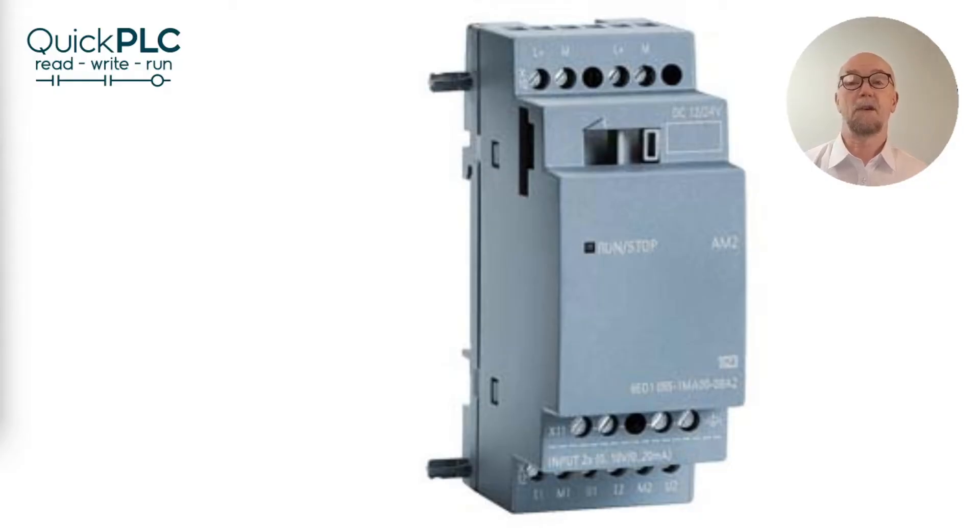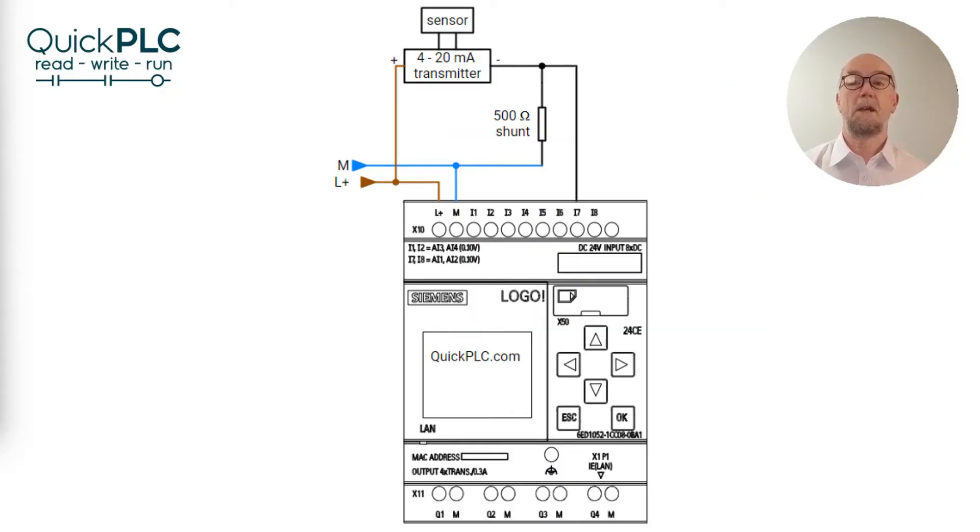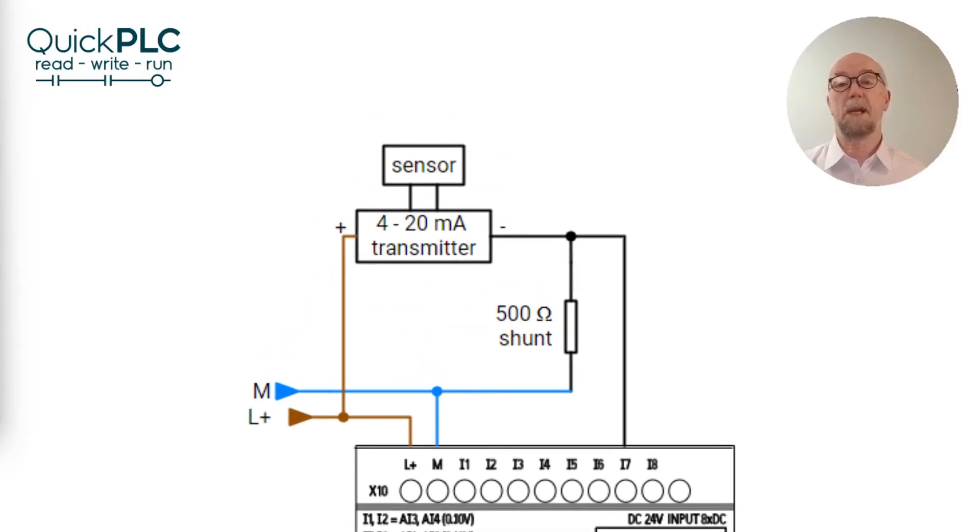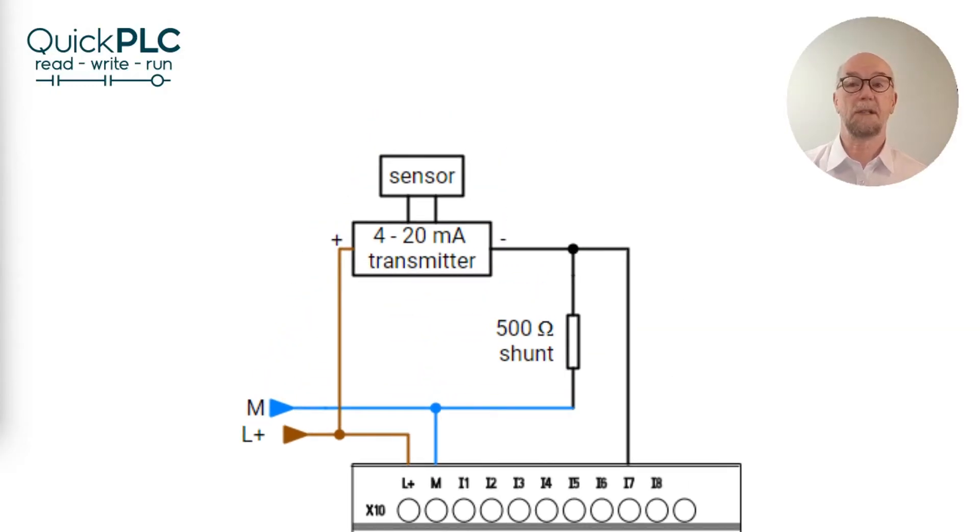The Logo range of components includes add-on 4 to 20 milliamp modules but if you have the basic module inputs to spare and you don't need electrical isolation from the digital inputs then we can use a resistor to convert from milliamps to volts. We can convert a 4 to 20 milliamp signal to 10 volt input by using a resistor. From Ohm's law we know that 10 volts at 20 milliamps will need 10 divided by 0.02 which equals 500 ohms.